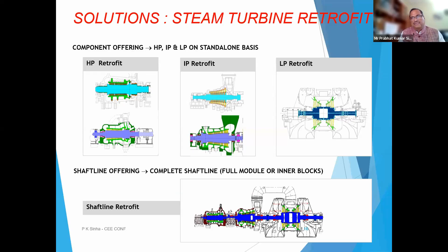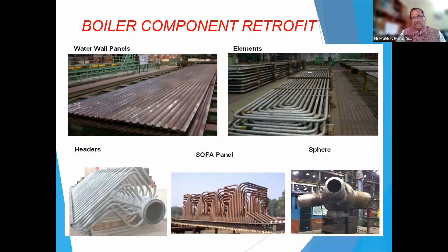Such retrofits have taken place very recently and successfully at one NTPC power plant, in Ramagundam, where three 200 megawatt units were running at least 10 to 15% below their nameplate rating. They have been brought up to nameplate rating parameters, and even the heat rate has improved. Upgradation in the boiler can also take place by improving the quality of material, which can reduce outages, etc. So these things are very much available in the market.